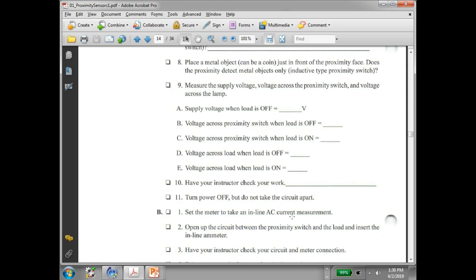Because it has to drop a voltage, right? This guy is powered up through the load. What did I say about what we're going to measure? Probably around 4 volts. But still, that's going to lead to 116 volts out there on the load, right? And most loads are designed to run at their rated voltage plus or minus 10%. So that gives us down to around 97 volts that these guys could run off of.